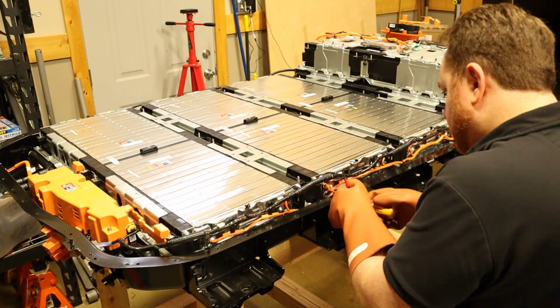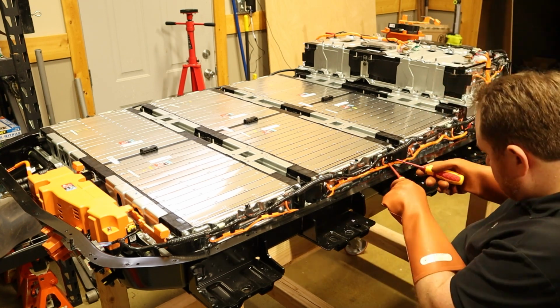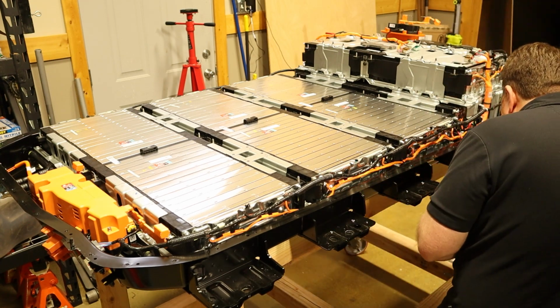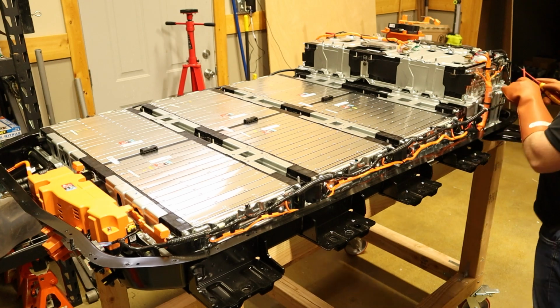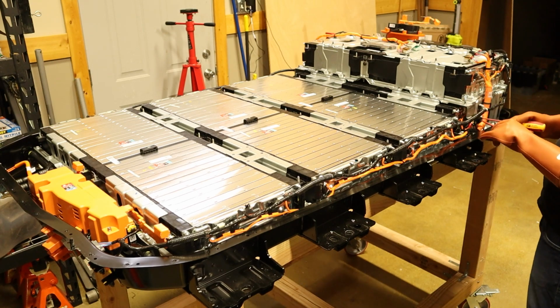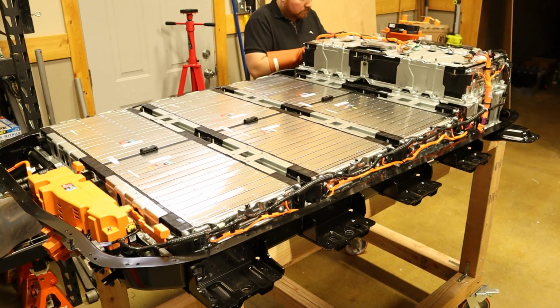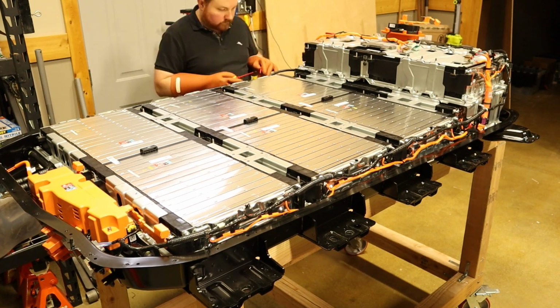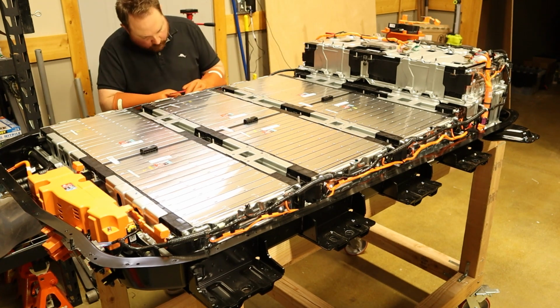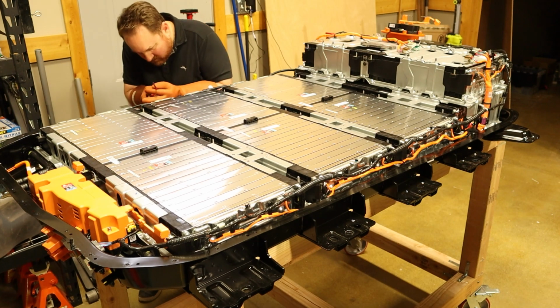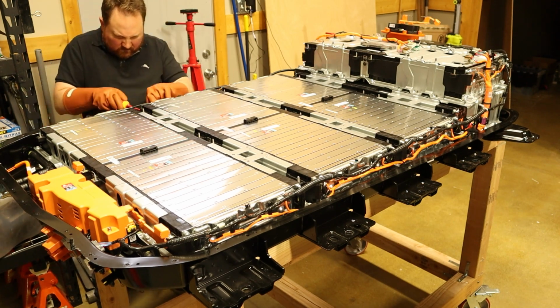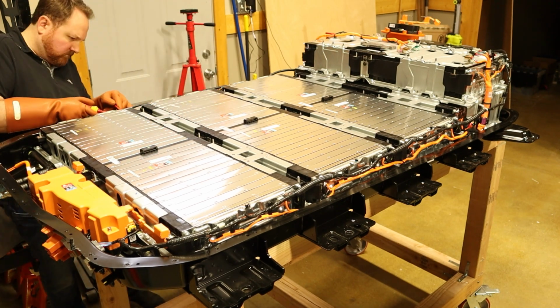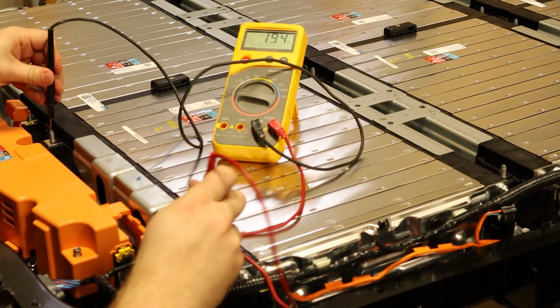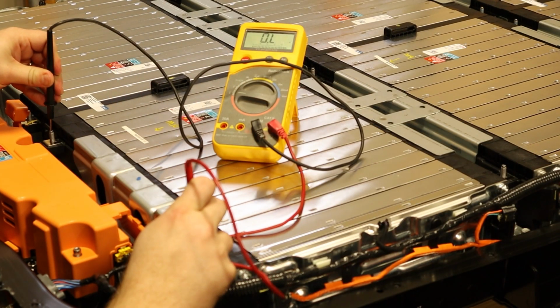When the bus bars are in place, all of the voltages of the modules add together. That's how we get 350 or 400 volts. But when they're removed, the maximum voltage from each module is only 40 volts, and I'm currently reading 35 volts. So the high voltage gloves are no longer required. However, each one of these batteries can still supply 1,000 amps at that voltage, so I still have to use insulated tools to prevent shorting anything out.